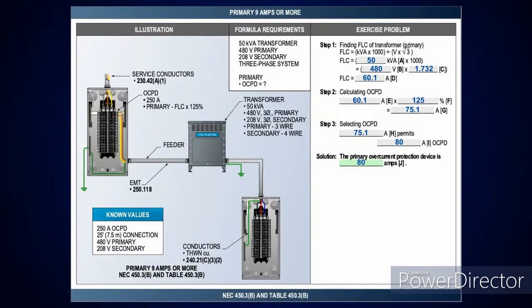Now, I'm going to look at the table in 450.3B, and if I'm doing primary only protection and I pick up the column where it's under primary protection and pick up a current of 9 amps or more, it tells me take it at 125%. And look there, there's that little superscript 1 right above it. So that means we're going to do what? Go up to the next standard size. So I'll take 60.1 times 125% gives me 75.1 amps. Go to table 240.6A, the next size above that is an 80 amp overcurrent device.